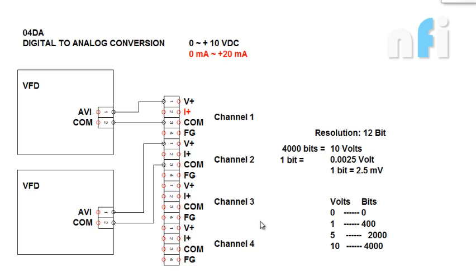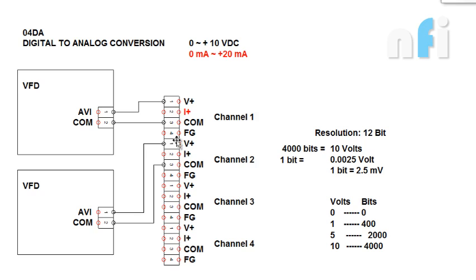Similarly we have the 4 channels, 1, 2, 3, 4, and this also has similar 4 terminals: V+, I+, and FG. FG is basically the functional ground. I forgot to explain - if you are having some noise signal in your A2D or D2A cards, you just have to connect ground to your FG which will reduce the noise signals.